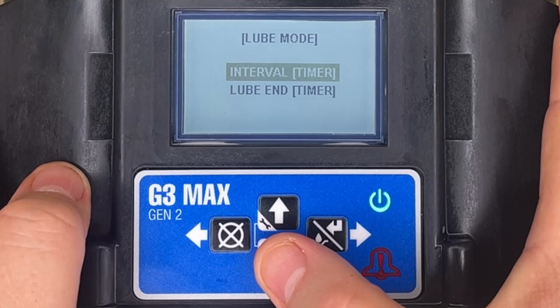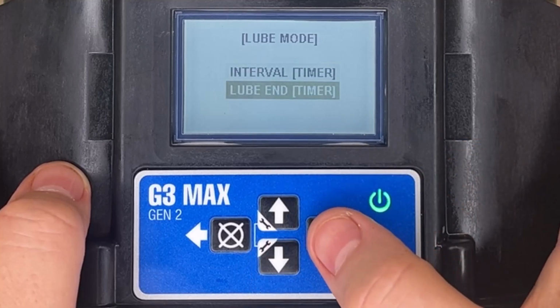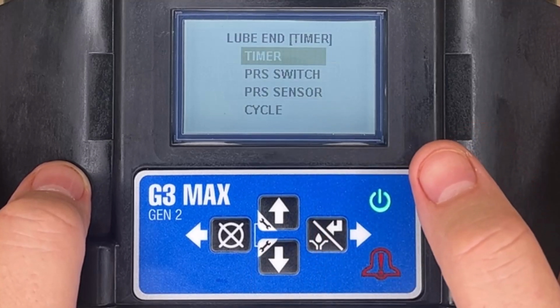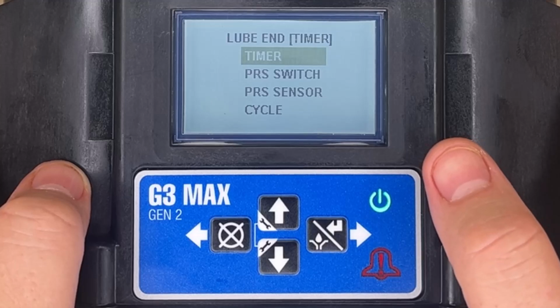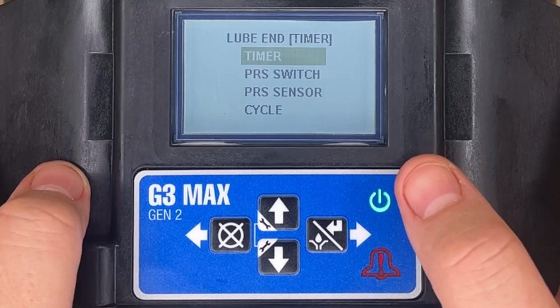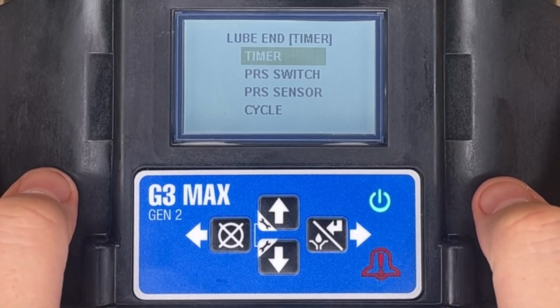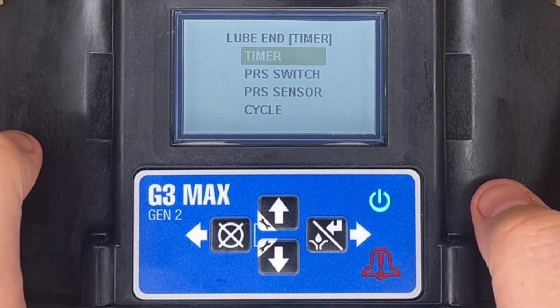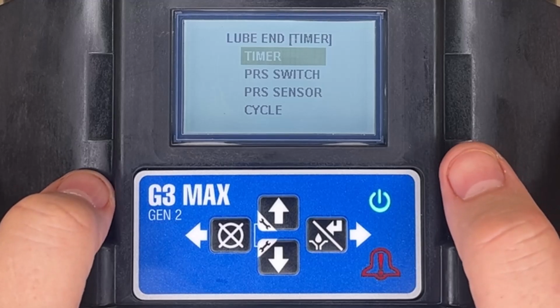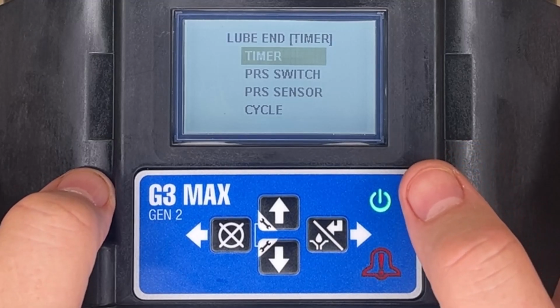And now the lube end is where we can choose between a timer, a pressure switch, a pressure sensor or transducer, or a cycle counter. A cycle counter is for series progressive systems, so we're not going to choose that. A timer would ignore any sensor input, so we want to make sure we choose one of the pressure inputs.